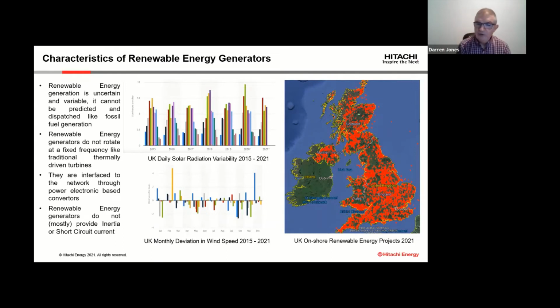Many, though not all, power electronic converters used on wind turbines today use what's called phase lock loops. They take a 50 hertz reference signal from the transmission system and use it to drive the output power electronics, matching and synchronizing the turbine's output with the grid.